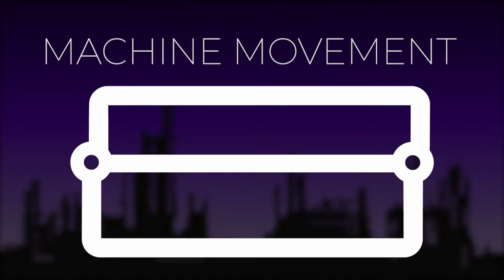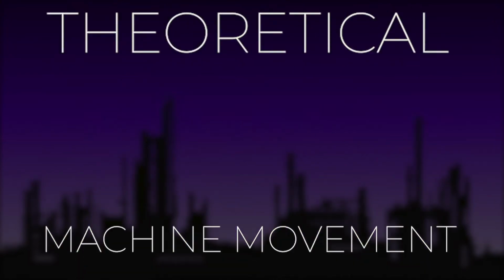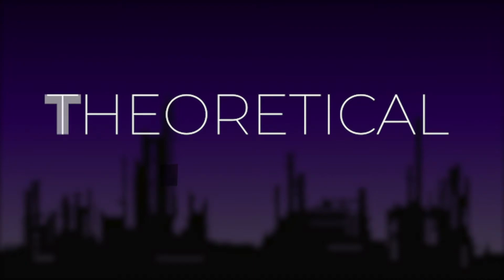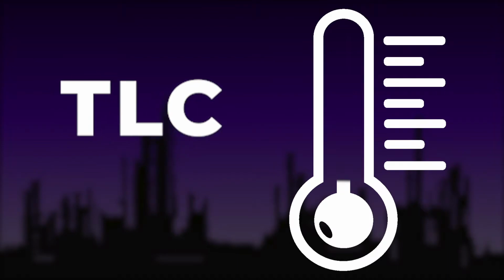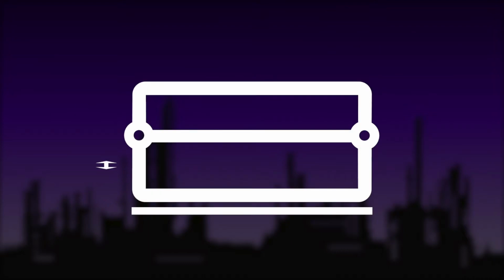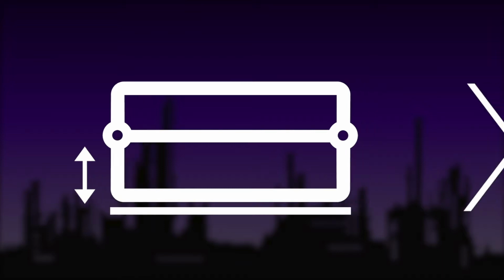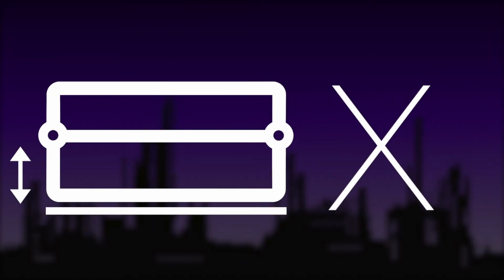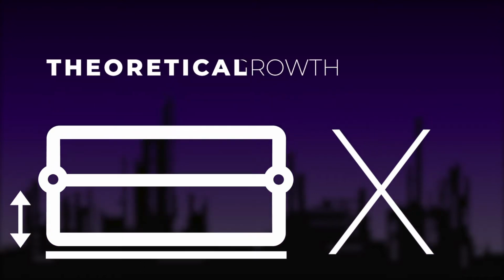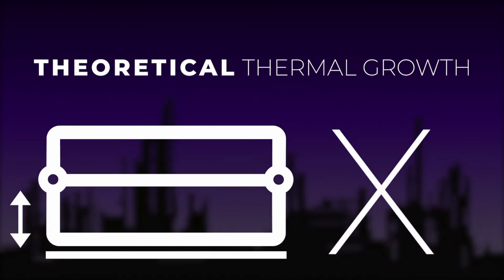the machine has moved. The next thing we can do is a theoretical or TLC calculation. With a TLC calculation, we take the change in temperature between the hot and the cold readings. We take the distance between the center of the machine shaft and the shim plate of the machine and the material constant. We multiply these together and will determine the theoretical thermal growth of the machine at the shaft.